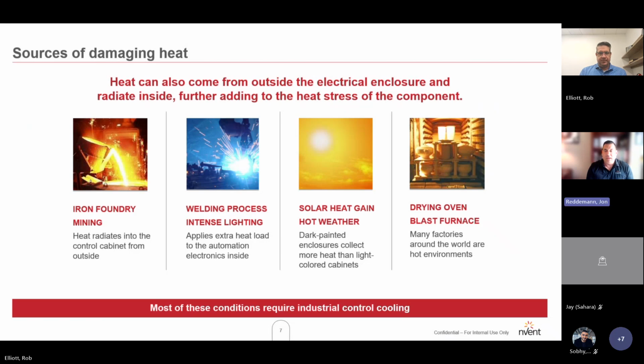So when we're looking at managing the thermal load of an enclosure, we have three potential heat sources. We have the components inside the enclosure that are potentially a source of heat. And if our ambient temperature is higher than our desired enclosure temperature, then we have that external ambient load onto the enclosure as a second heat source. And if we are outdoors in direct sunlight, that solar load would be a third source for us, right?